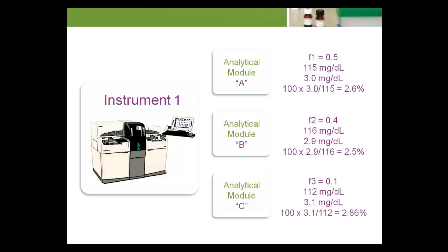The mean glucose levels for the three modules are 115 mg per deciliter, 116 mg per deciliter, and 112 mg per deciliter. The standard deviations are 3.0 mg per deciliter, 2.9 mg per deciliter, and 3.1 mg per deciliter, giving individual coefficients of variation of 100 times 3.0 over 115 equals 2.6%, 100 times 2.9 over 116 equals 2.5%, and 100 times 3.1 over 112 equals 2.86%.